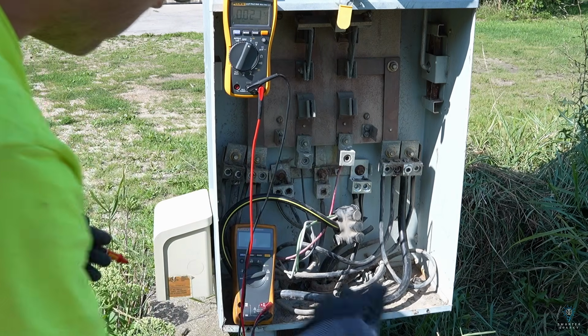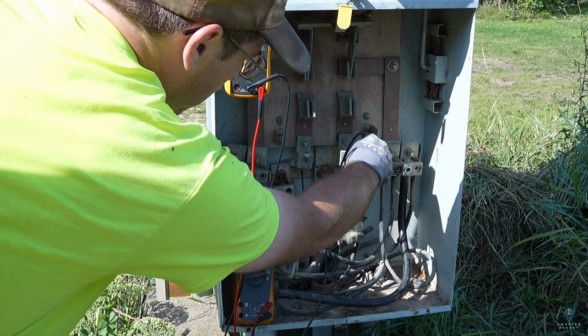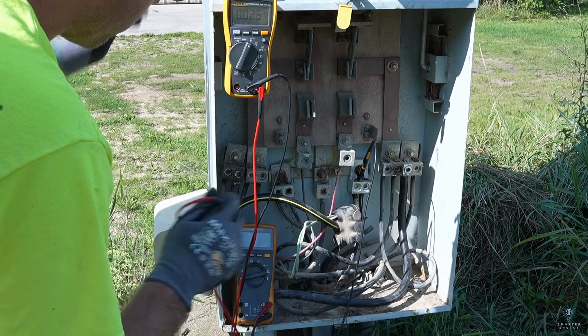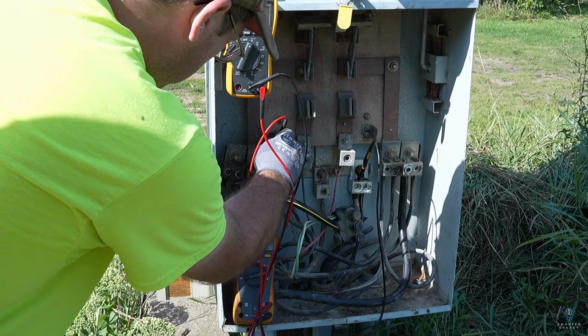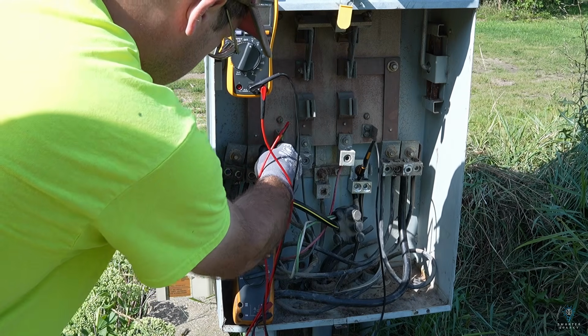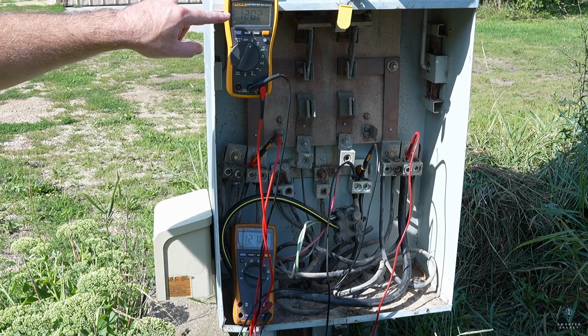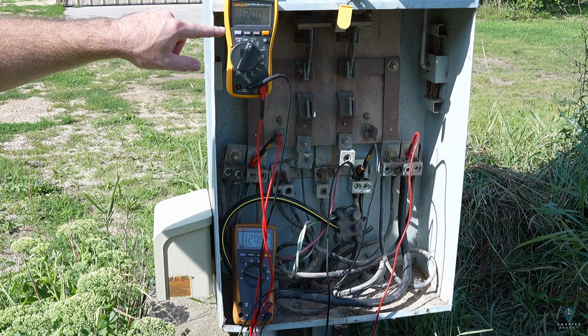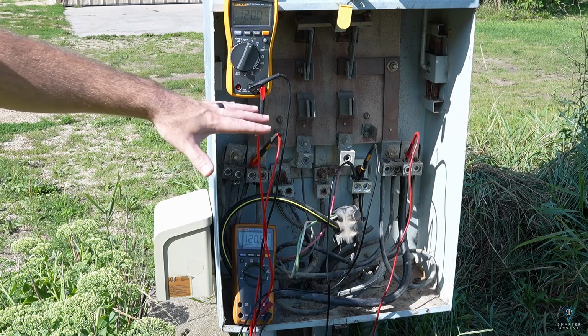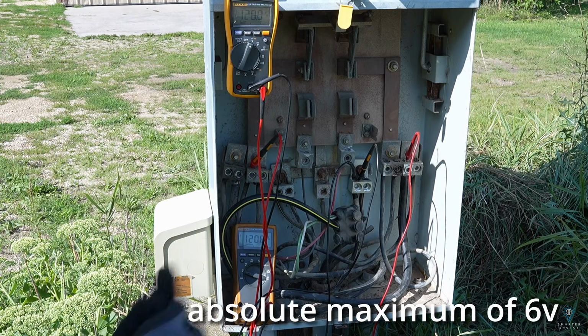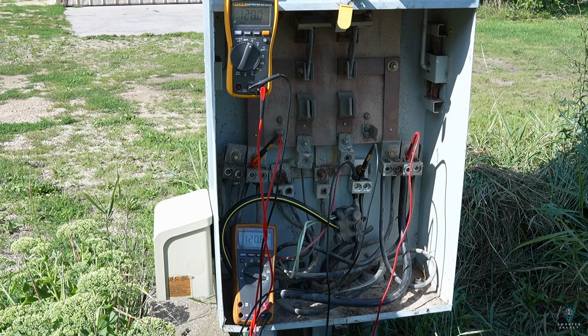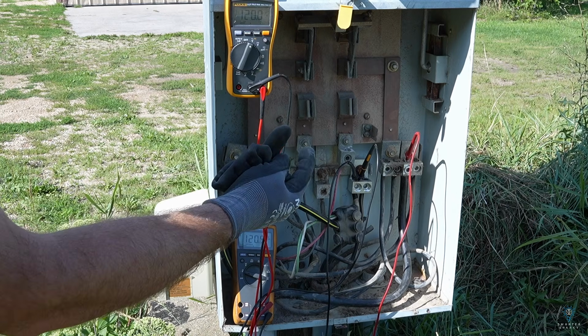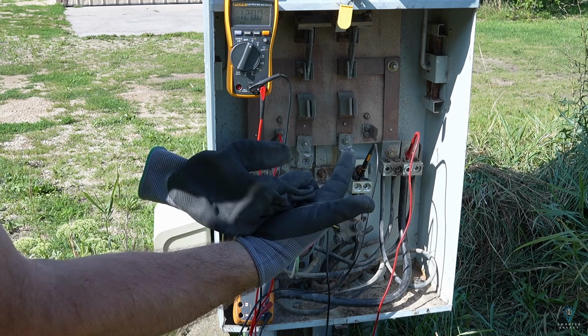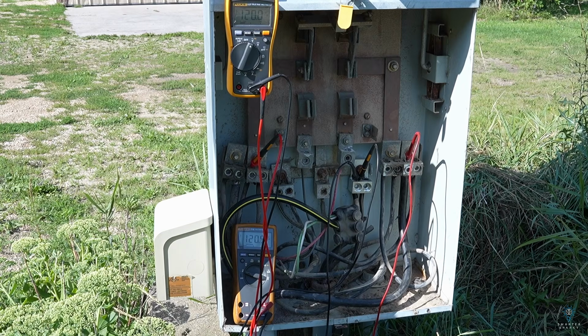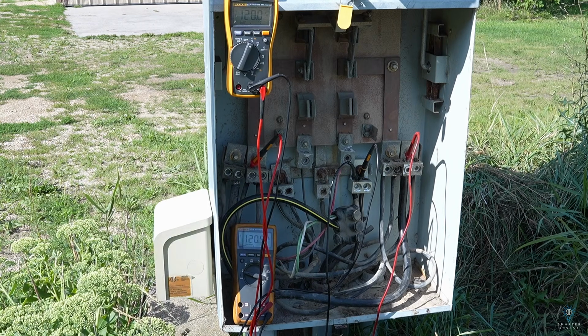So I actually feel that is already solving our problem. But let's actually do the same test that we did before. So I'll shove one probe in the neutral, and I'm gonna shove the other probe up here in the hot, one of the hots. We got 120.9, 120.1. So there is a little bit of a difference, but that's normal. Normal on this would be about 4 volt voltage drop. So I would say we are good. Now the power's been off in the house for a while, so the sump pump's no doubt kicked on, dehumidifier. Air conditioners are off right now. I feel pretty good about this. Let's go inside and double check our voltages.